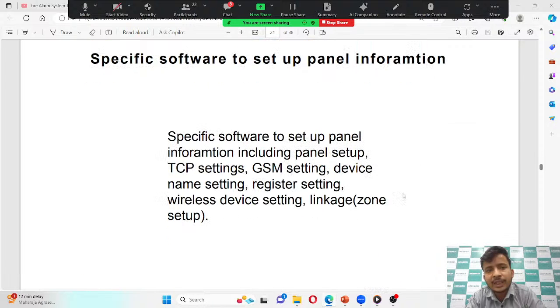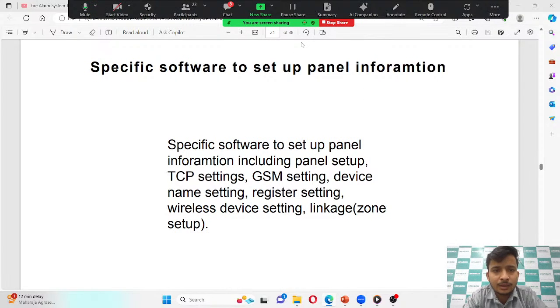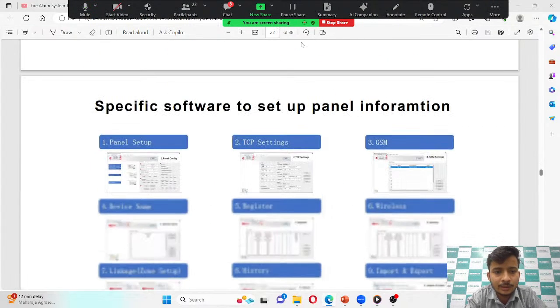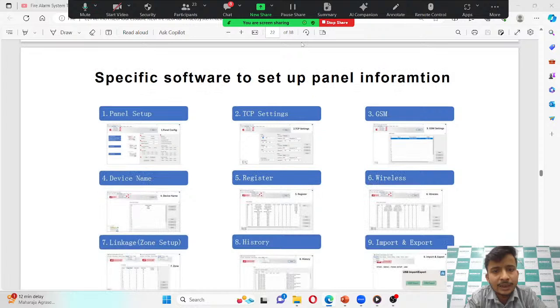Then we have specific software for all the configuration of our fire panel. We have the panel setup option, then the TCP/IP settings option, then the GSM configuration options, then device name, where you can give a name to any particular device. Then register, for adding all the devices. Once you give the address to the devices, you can auto search the devices through the software, and it will automatically detect the devices which are available in a loop.